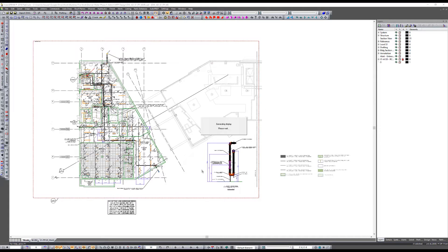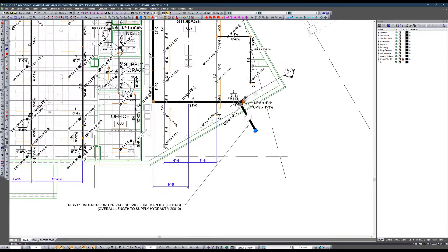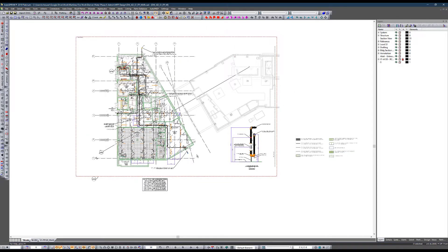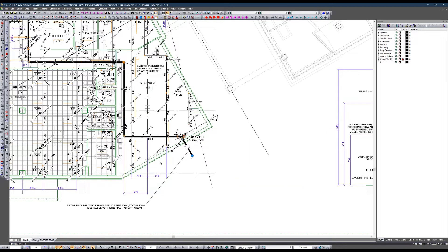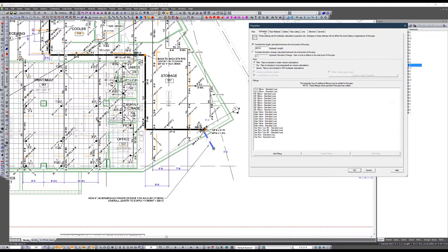Generally, for underground I don't like drawing all of it — this system was incredibly extensive, looping around the building and hitting a couple of different hydrants. It was a water model provided by the water department and it was too time-consuming to draw all of that. So instead, in the properties of this piece of pipe, I overrode the length — rather than calculating as seven foot eight and a half, I set it to 200 feet — and then added all of the fittings and valves, which were a significant number.